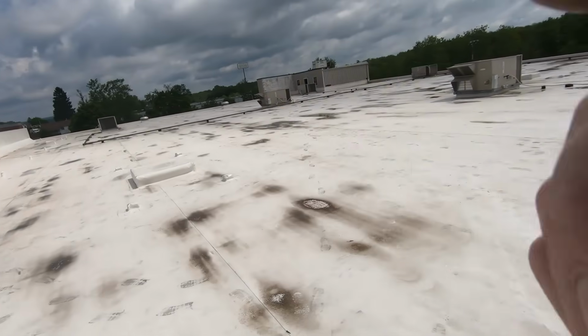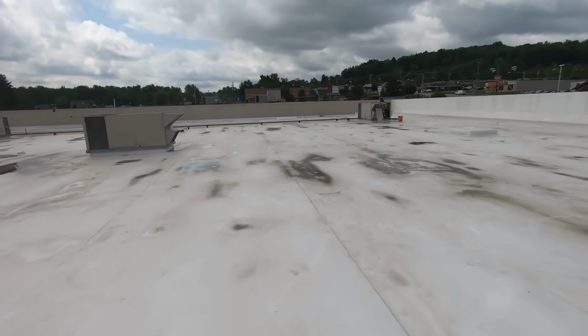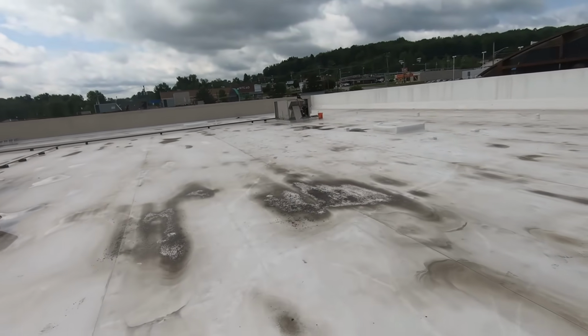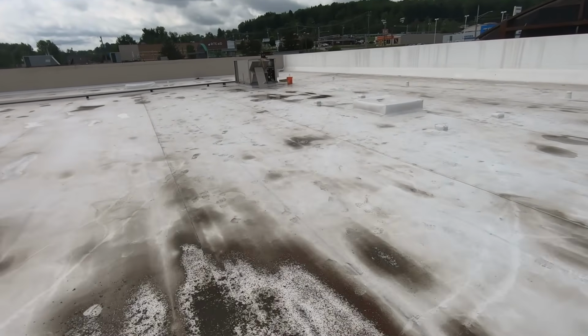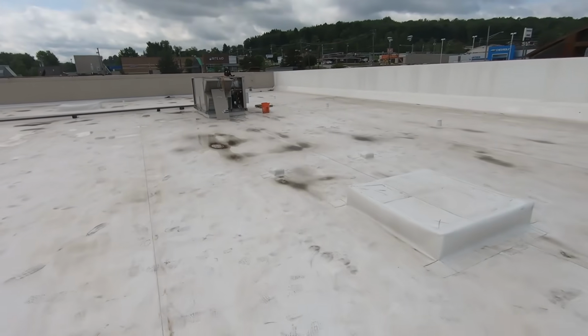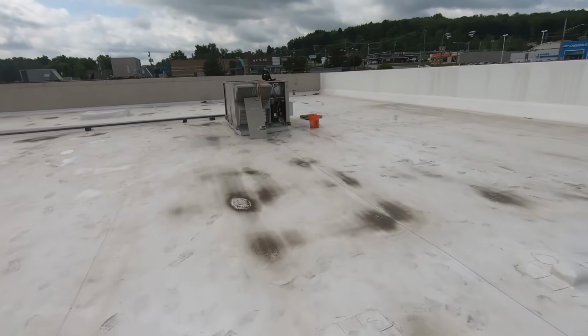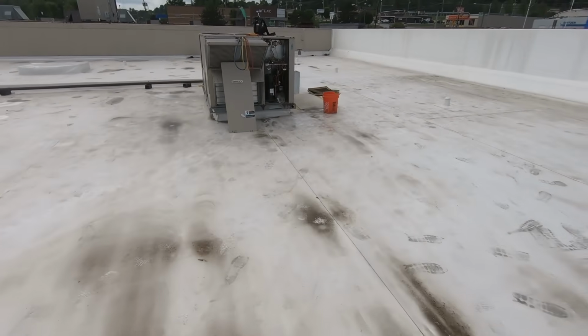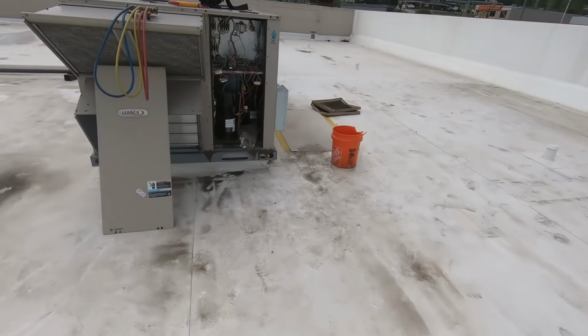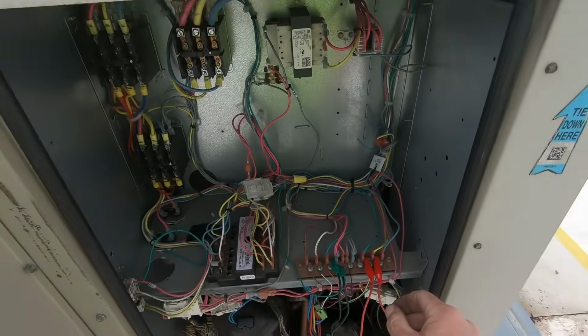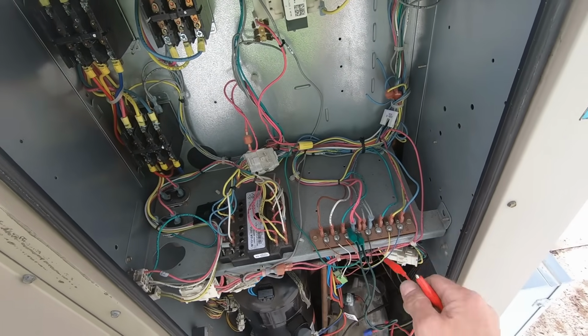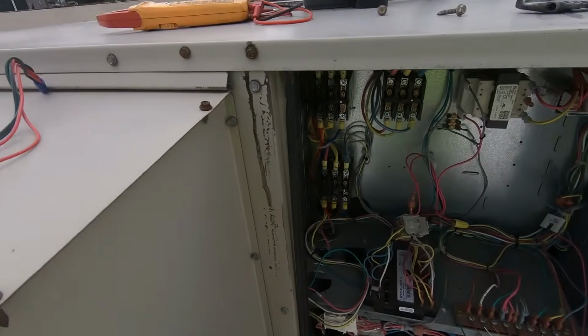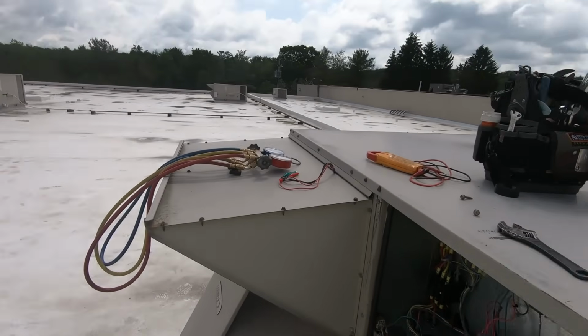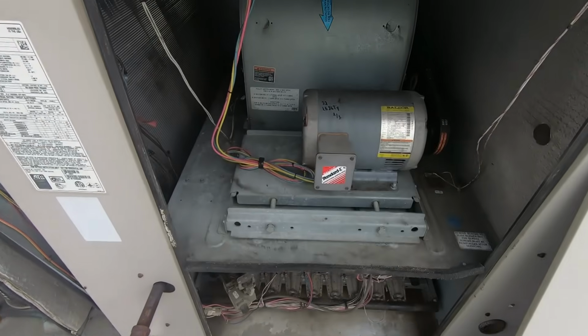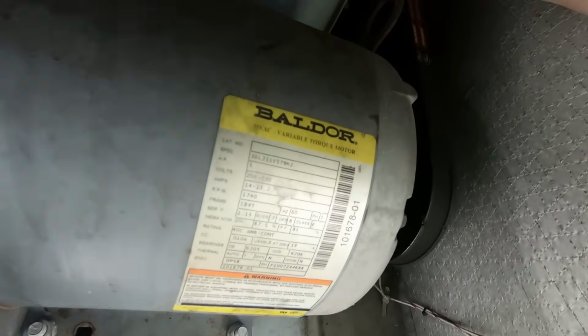I'm heading that way. Okay, I got that one opened up. This guy's been running for a minute. I'm just going to button it up. We'll come back and clean it. Mechanically, I don't see any major problems at the time. And we'll go from there. Wonder if this thing's going to be calling. It's not the hottest day out, so more than likely, nope. All right, let's button this back up. We're just going to keep plugging away here. Okay, so we have power on this one. That's good. I did shut the disconnect off and confirm that power was off.